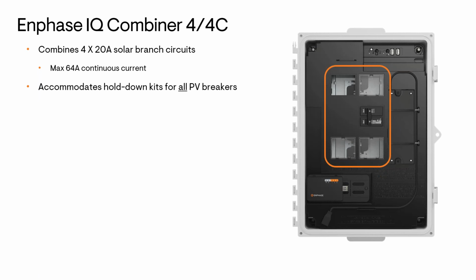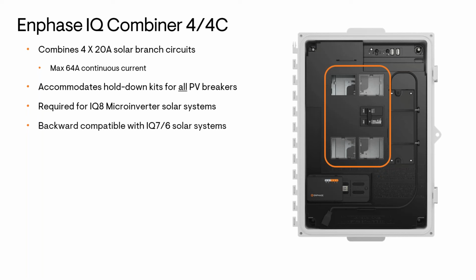The NEC requires any reverse-powered circuit breakers to have a fastener. And this wasn't needed with IQ7 and earlier models or for other brands of standard grid-tied inverters, because there's an exception to the NEC rule for grid interactive inverters, since they're designed to instantly turn off if disconnected from the grid. So an inverter disconnect was sufficient. However, whenever the IQ8 is being used in a backup configuration and therefore grid forming, the PV breakers must be bolted down with hold-down kits. So for this reason, the Combiner 4 or 4C has to be used with IQ8 solar systems in backup power configurations. It can also be used for solar-only systems without backup capability, and in that case the hold-down kits wouldn't be required. It's backward compatible with IQ7 and earlier systems.